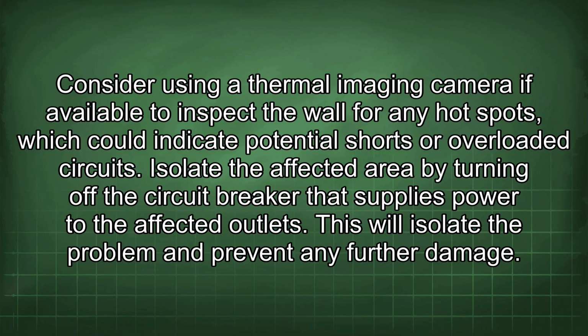Consider using a thermal imaging camera, if available, to inspect the wall for any hot spots, which could indicate potential shorts or overloaded circuits. Isolate the affected area by turning off the circuit breaker that supplies power to the affected outlets. This will isolate the problem and prevent any further damage.